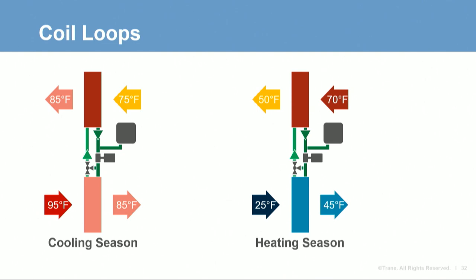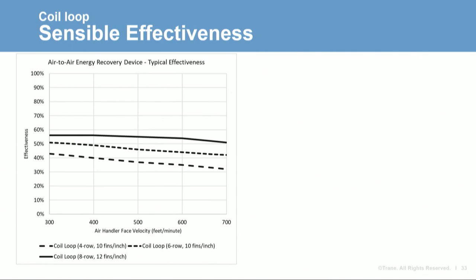In the heating season, warm exhaust air heats the fluid in the coil, which is circulated to the coil in the ventilation airstream, and the outdoor air is heated. Looking at individual coil performance, a chart shows sensible effectiveness on the vertical axis and coil face velocity on the horizontal axis. Three coils are plotted: an 8-row 12 fins per inch coil at top, a 6-row 10 fins per inch coil in the middle, and a 4-row 10 fins per inch coil at the bottom.